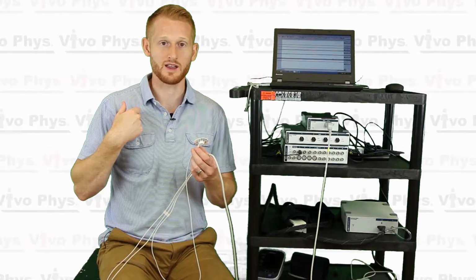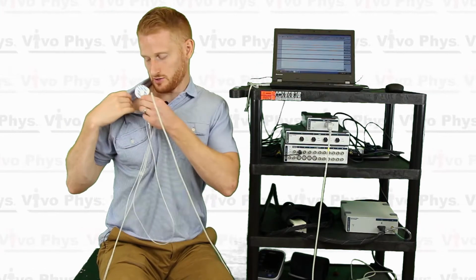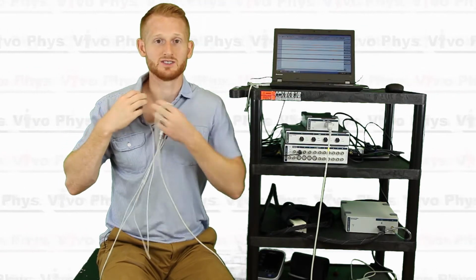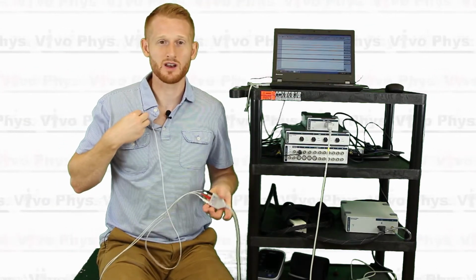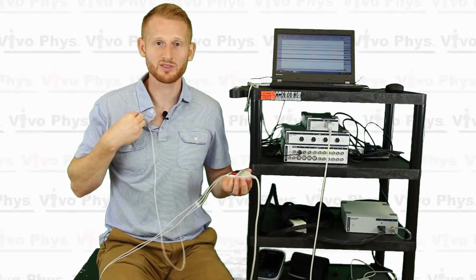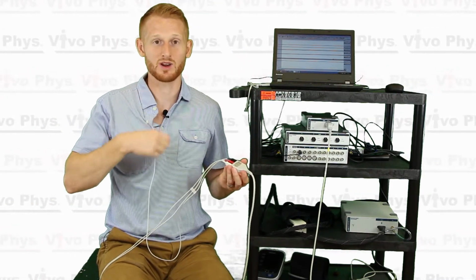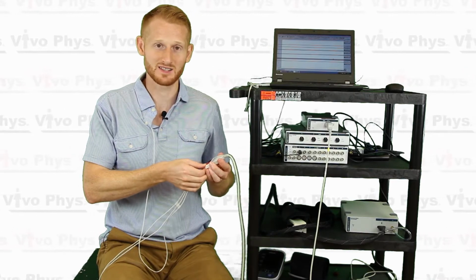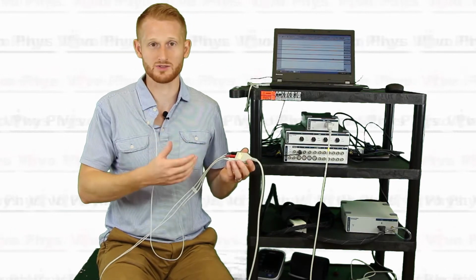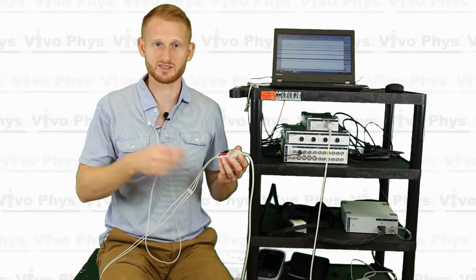So this one here is the negative electrode. I'm going to put it on my upper right-hand side of my chest, so I'm just going to go down my shirt here a little bit and place that just like that. Of course, if you want to have the best connection possible, you'd want to clean the skin and abrade the skin, remove some dead skin cells. But for a real quick introduction like this, I'm just going to place it right on.